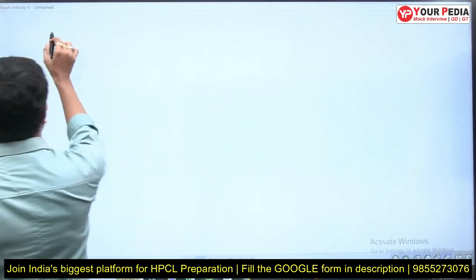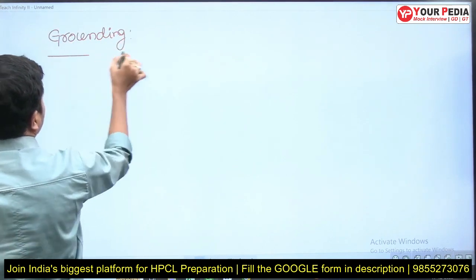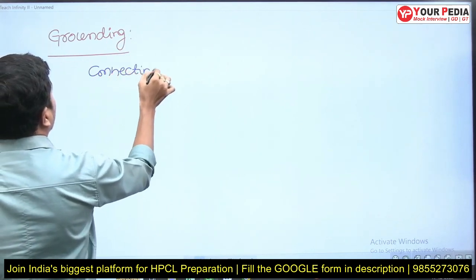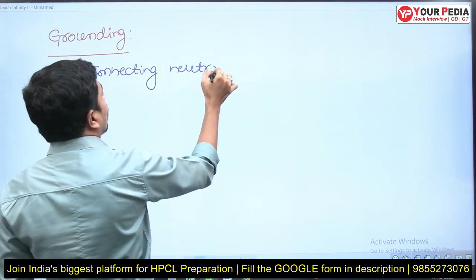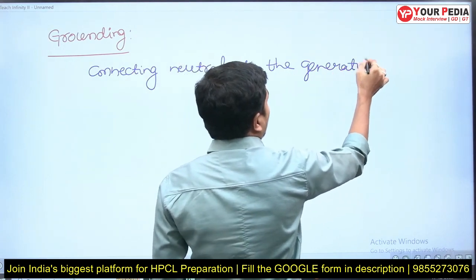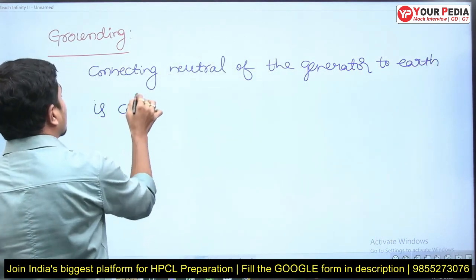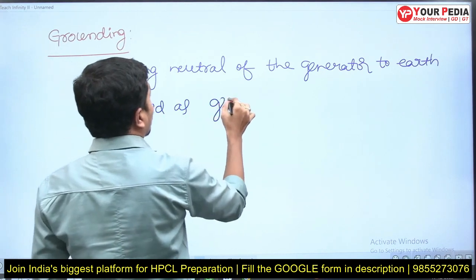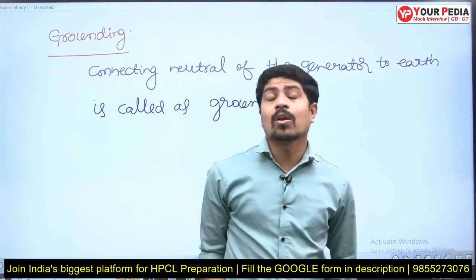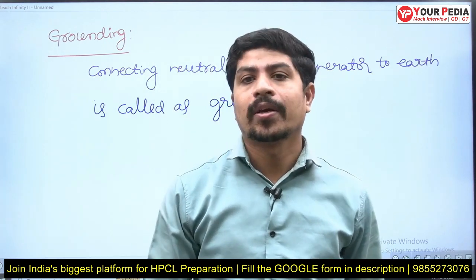So let me write: grounding means connecting the neutral of the generator to earth — this is called grounding or neutral grounding. There are several methods of neutral grounding: resistance grounding, reactance grounding, Petersen coil grounding, and solid grounding. For different applications, different grounding methods are used.